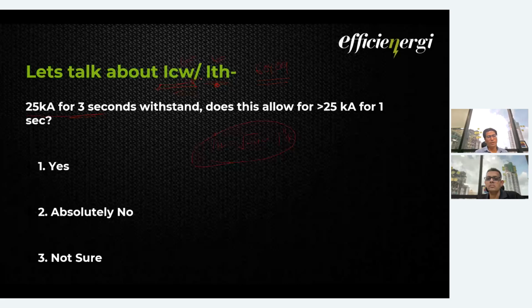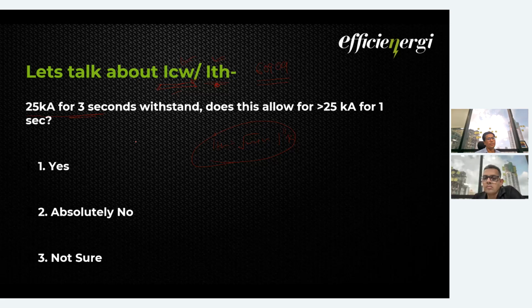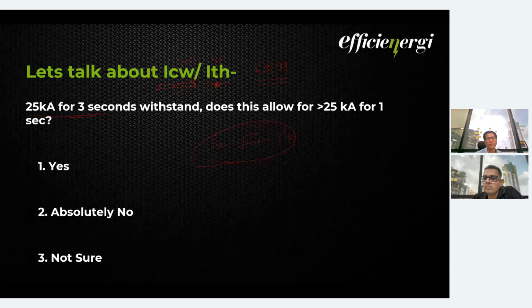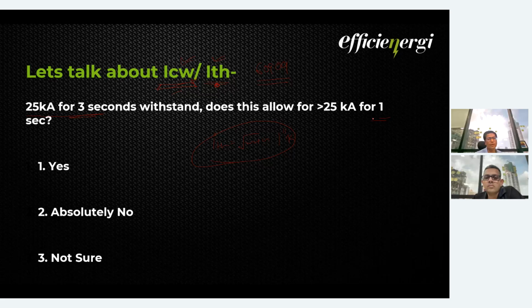Okay, you all must know that for a breaker we say 25 kiloampere, 3 seconds. So does this allow more than 25 kiloamperes for 1 second? What would be your answer for this? Okay, the poll is displayed. So what do you think? 25 kiloampere 3 seconds withstand is there, but I have a breaker which can clear in 1 second. So can we have more than 25 kiloampere?